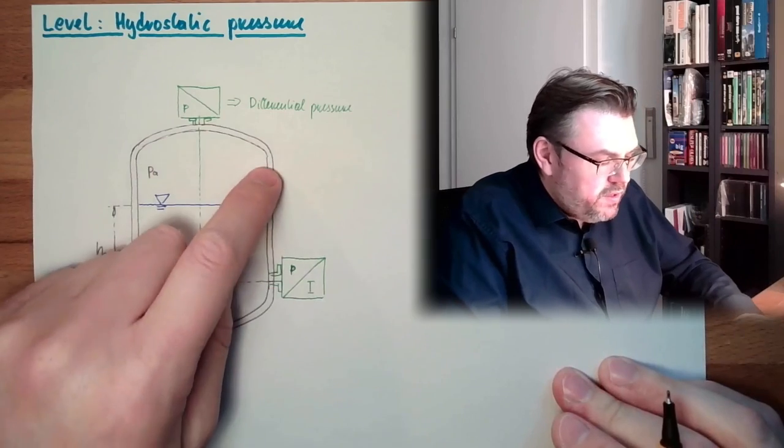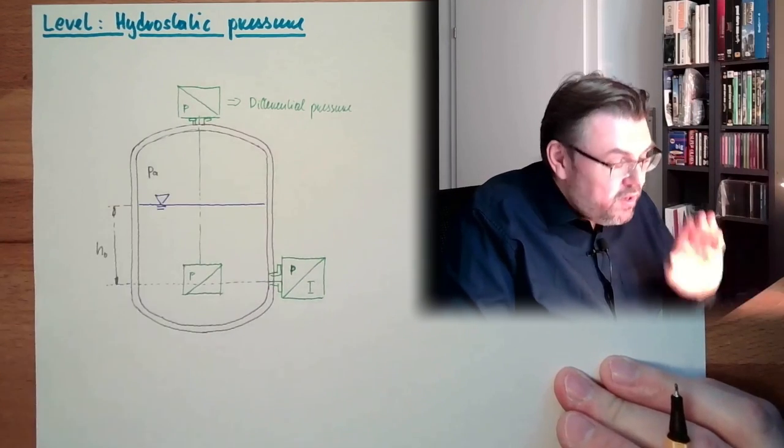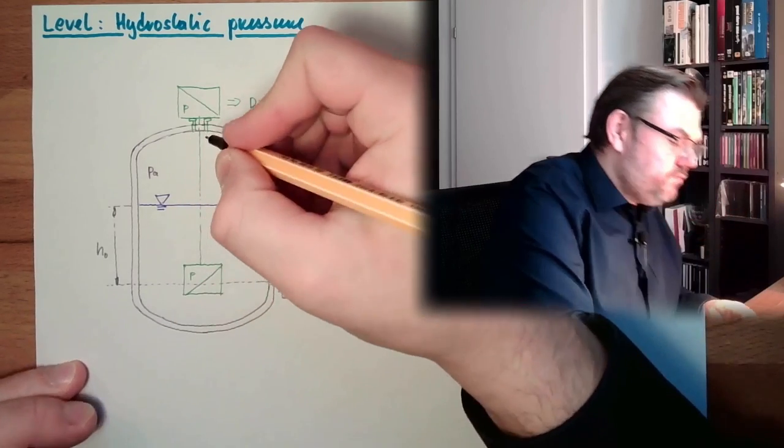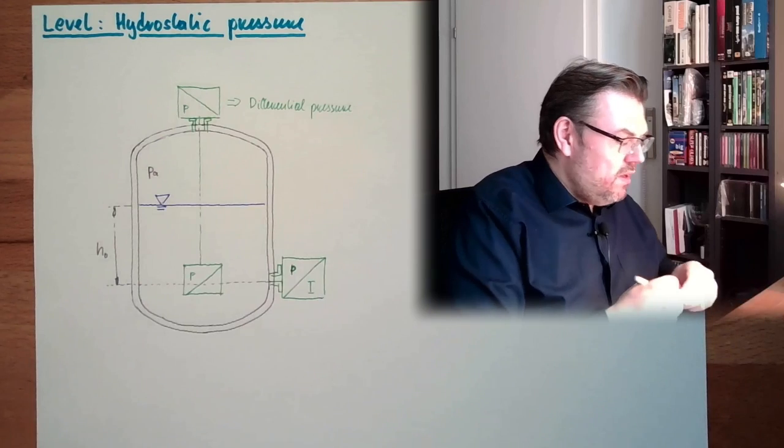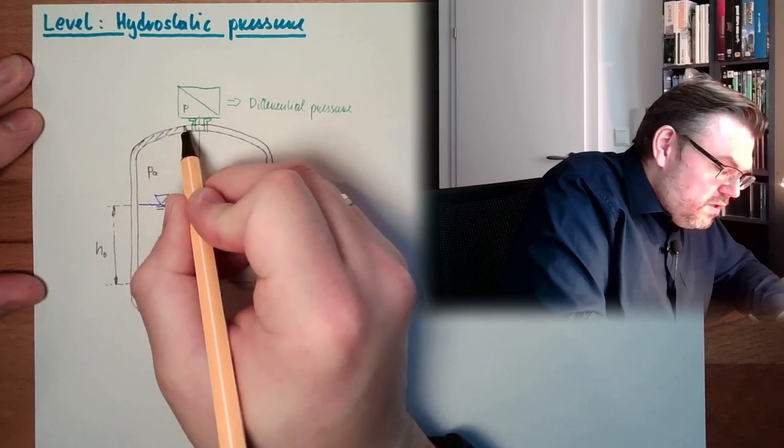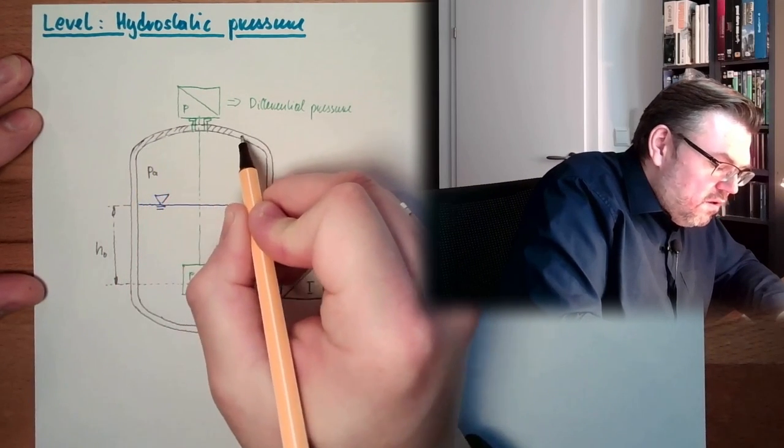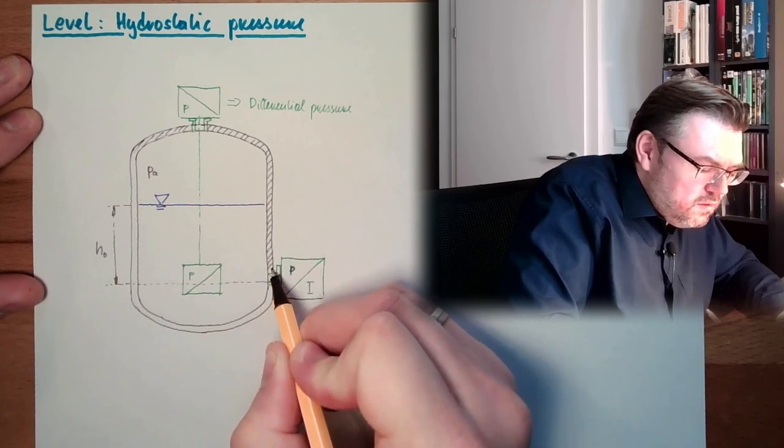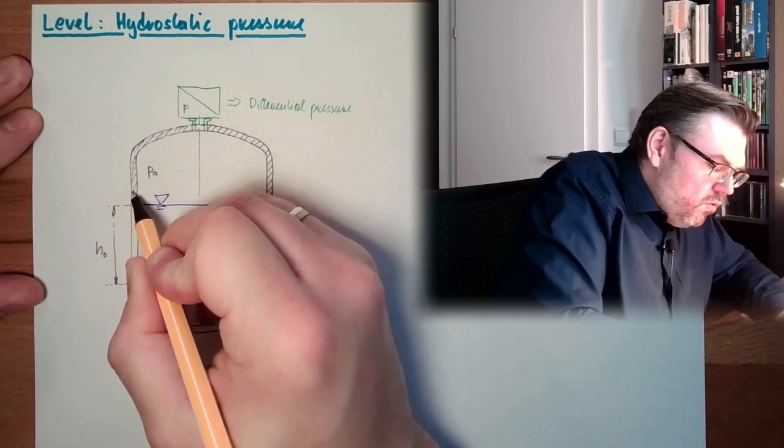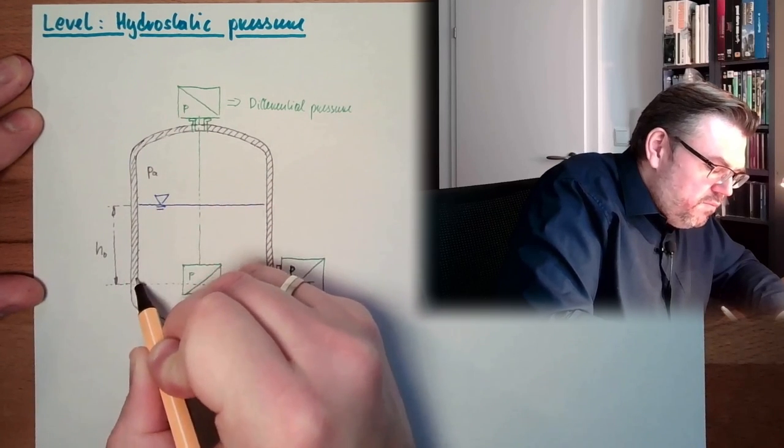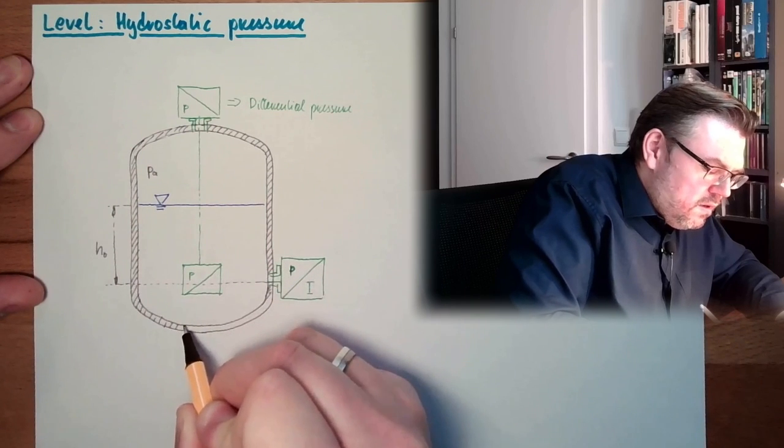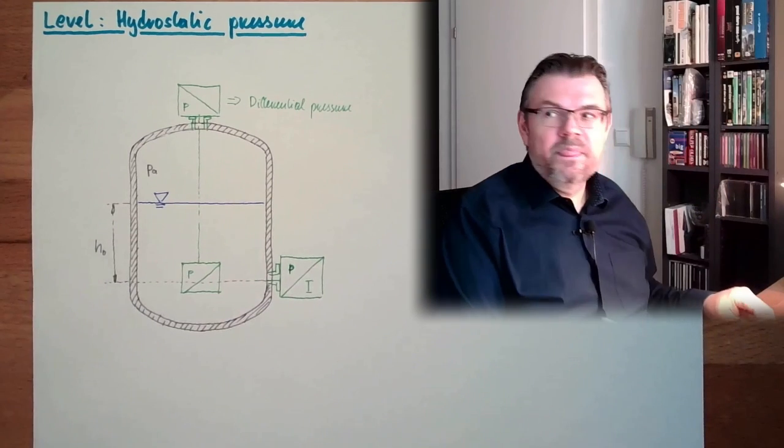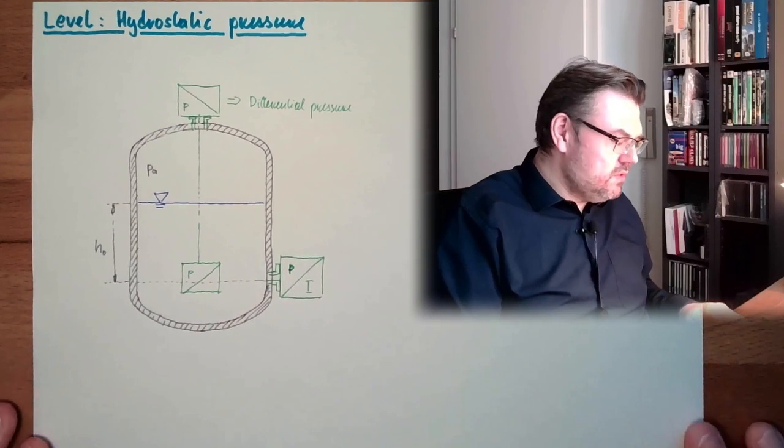We could also measure here a second time and make the differential pressure. And so that there are several possibilities to do this. So this is how this is working. So just measure the pressure. And because of the density, the weight of this, we know the hydrostatic pressure which should be in there and then we can calculate the level.